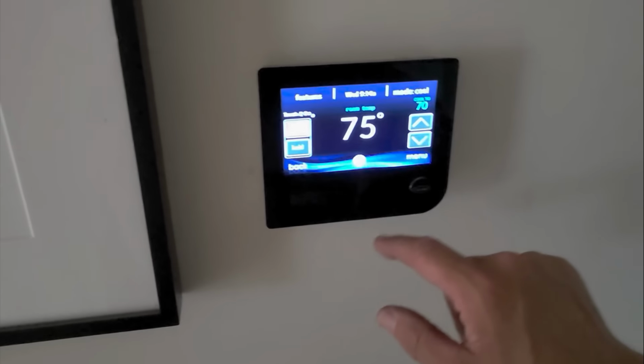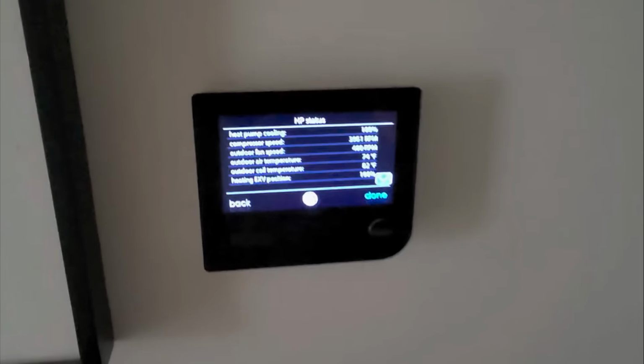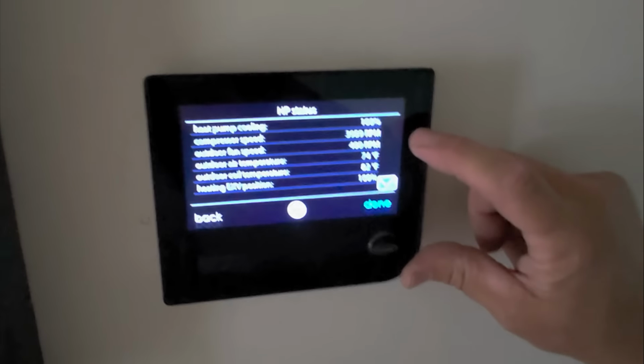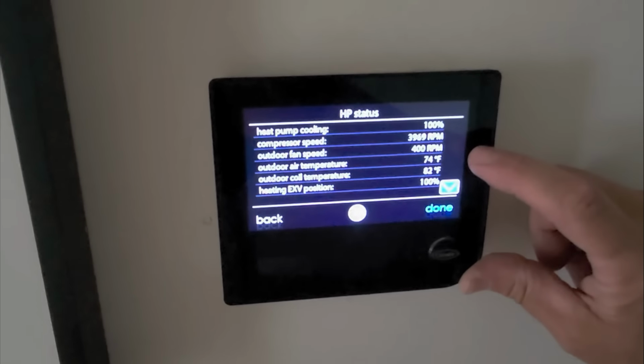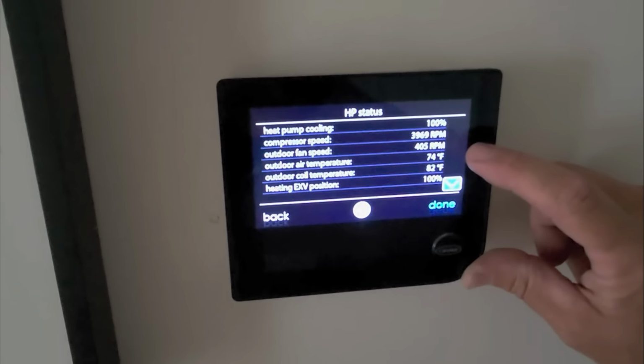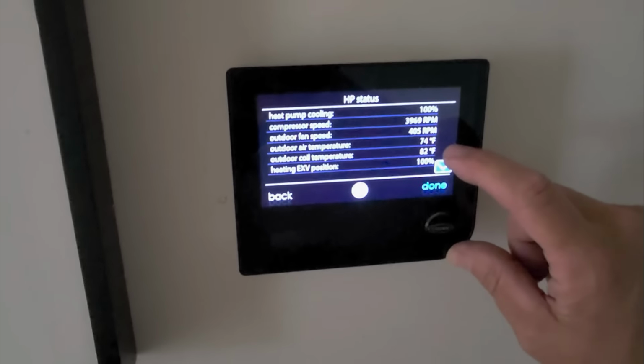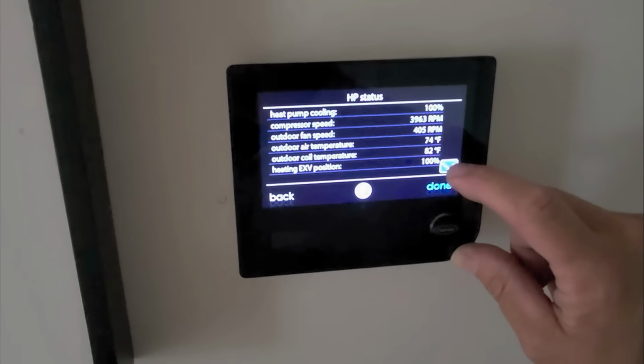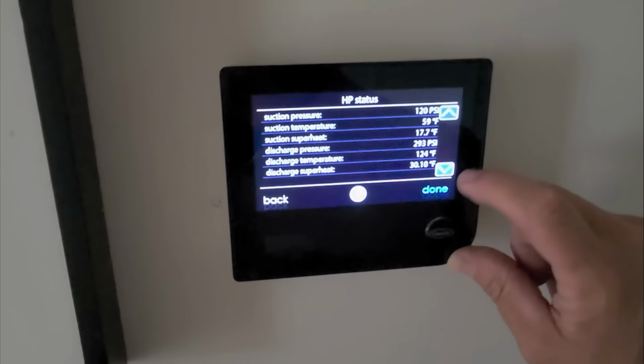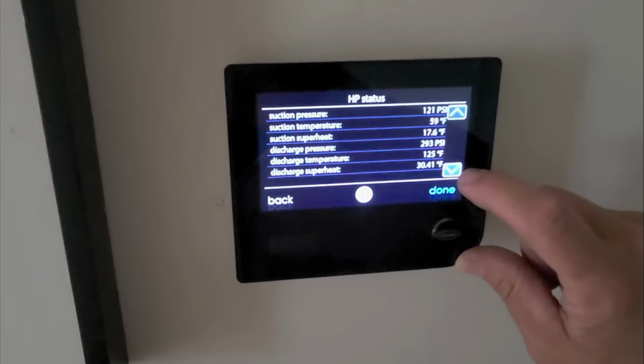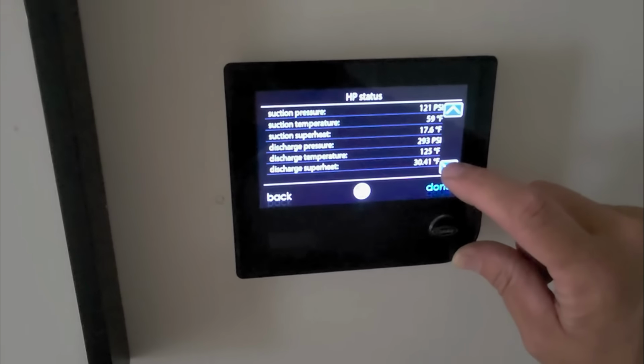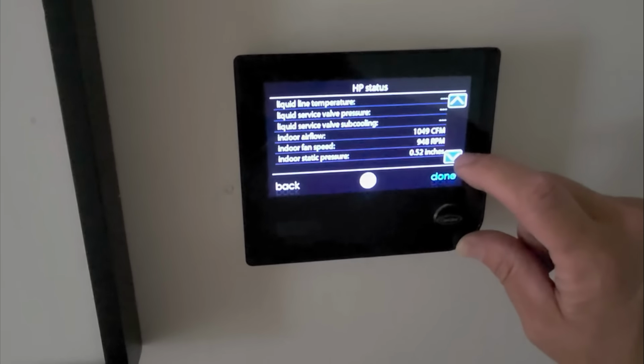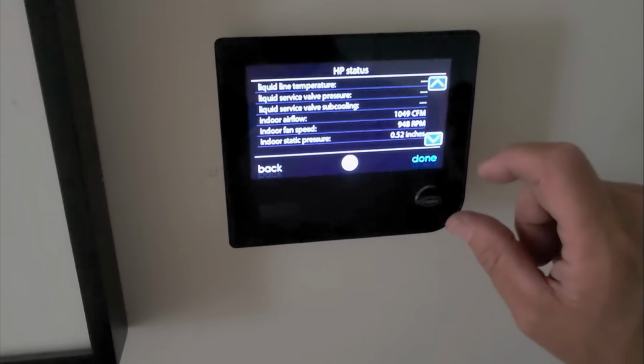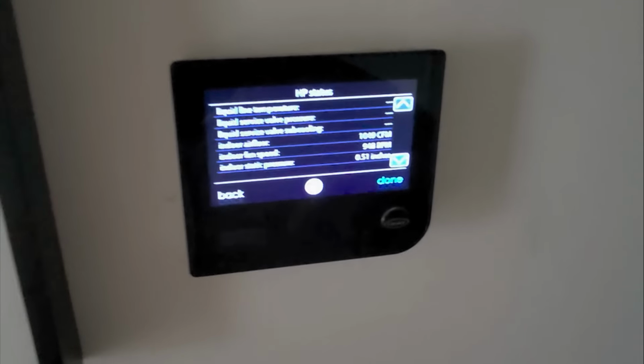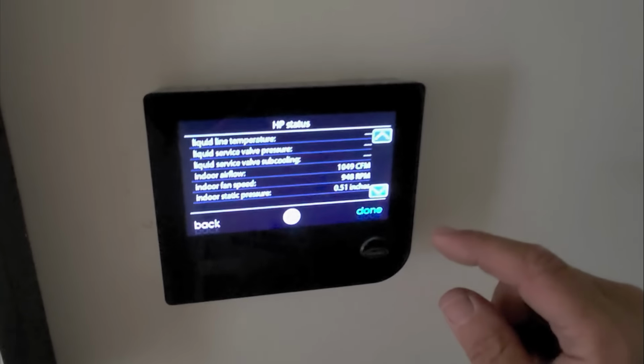All right. Good. All right, right now we're at 100%, a little under 4,000 RPMs. The outdoor fan speed 405, outdoor temperature 74, the coil temperature 82, and that EXV, that electronic expansion valve, is fully open. Okay. Indoor static pressure 0.52 inches at 1049 CFM.